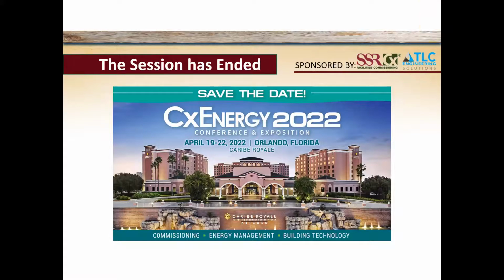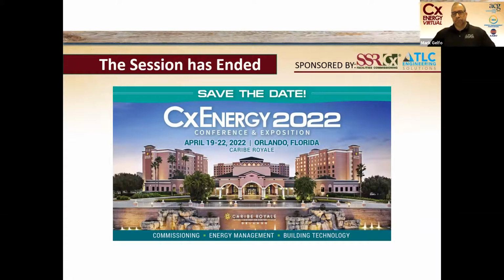Next question: does the generator need to be a certain size before load bank testing is required? I don't think so. NFPA 110 defines emergency gen sets by the load they serve, not by capacity, as far as I'm aware.